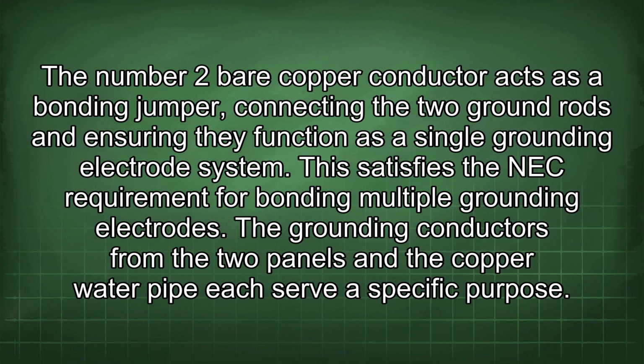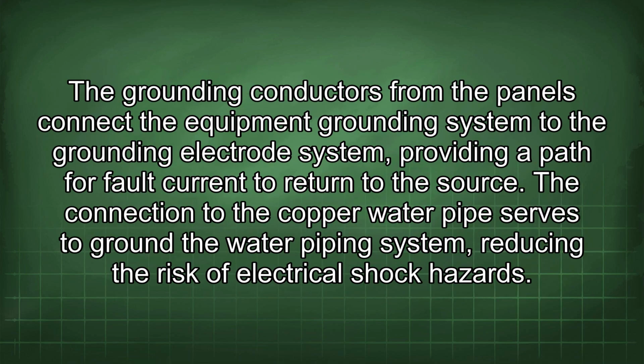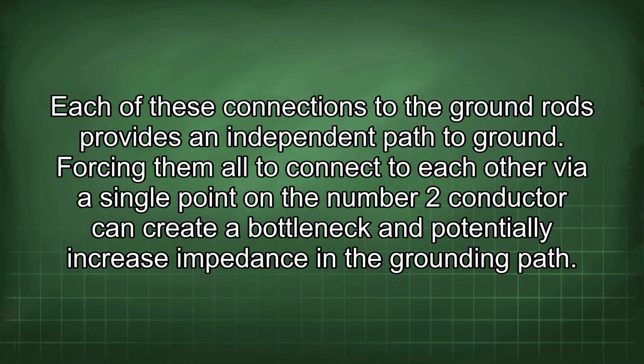The number 2 bare copper conductor acts as a bonding jumper, connecting the two ground rods and ensuring they function as a single grounding electrode system. This satisfies the NEC requirement for bonding multiple grounding electrodes. The grounding conductors from the two panels and the copper water pipe each serve a specific purpose. The grounding conductors from the panels connect the equipment grounding system to the grounding electrode system, providing a path for fault current to return to the source. The connection to the copper water pipe serves to ground the water piping system, reducing the risk of electrical shock hazards. Each of these connections to the ground rods provides an independent path to ground.